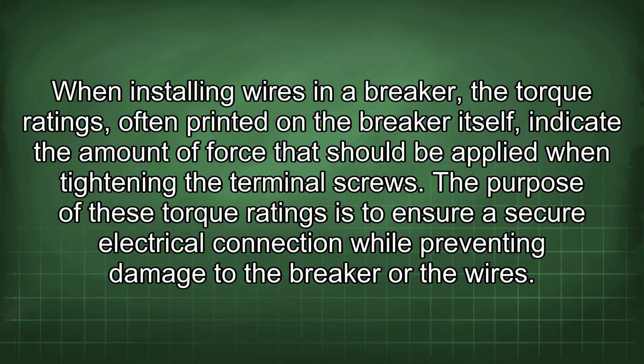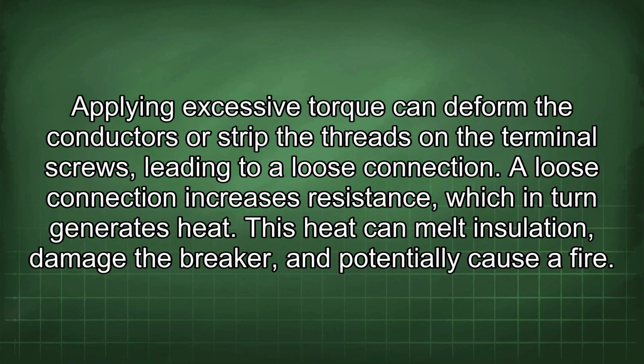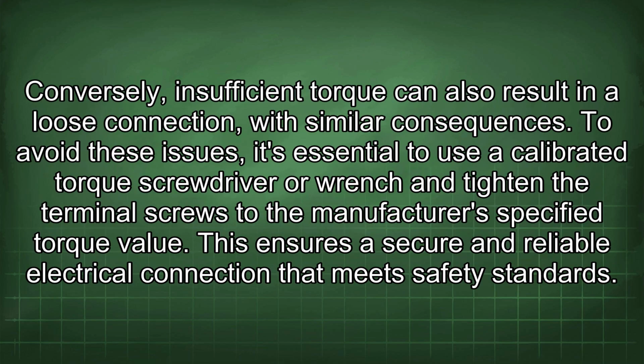When installing wires in a breaker, the torque ratings, often printed on the breaker itself, indicate the amount of force that should be applied when tightening the terminal screws. The purpose of these torque ratings is to ensure a secure electrical connection while preventing damage to the breaker or the wires. Applying excessive torque can deform the conductors or strip the threads on the terminal screws, leading to a loose connection. A loose connection increases resistance, which in turn generates heat. This heat can melt insulation, damage the breaker, and potentially cause a fire. Conversely, insufficient torque can also result in a loose connection, with similar consequences.